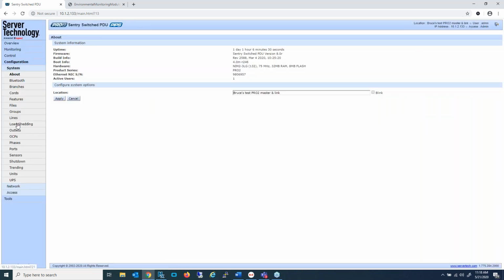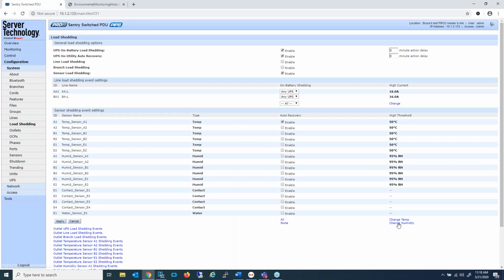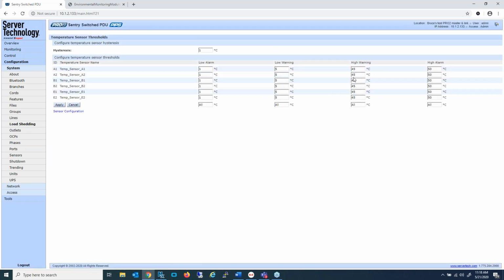Go back to configuration, load shedding, and use the shortcut to get to the thresholds. The warning threshold always needs to be lower than the alarm threshold, so I have to change both, but it is the high alarm that is the trigger. So I'm setting it for 22 degrees, which is under 24. The moment I click apply, the sensor will go into a high alarm state, and we won't actually see it because I won't be quick enough, but we will see that the outlets have changed their states.